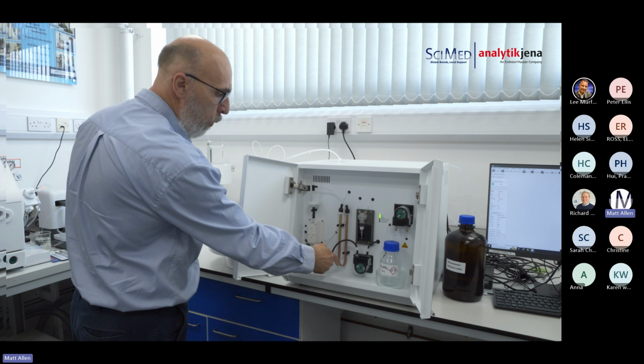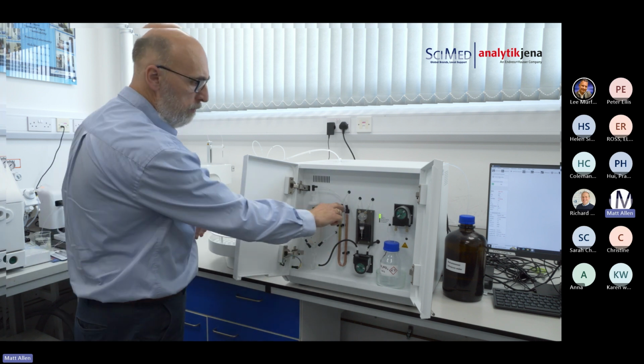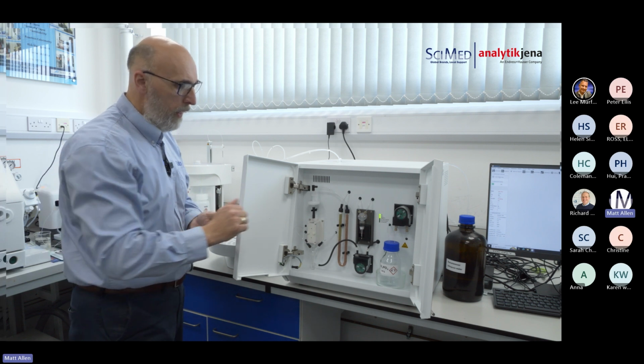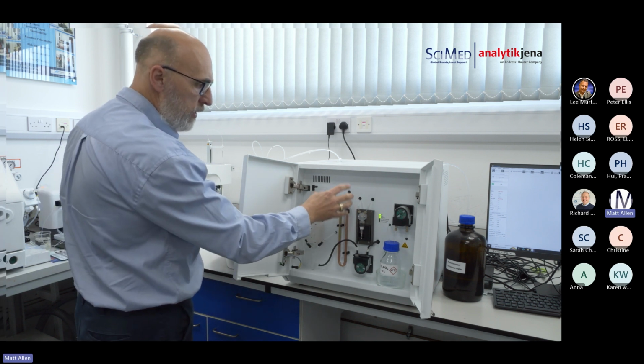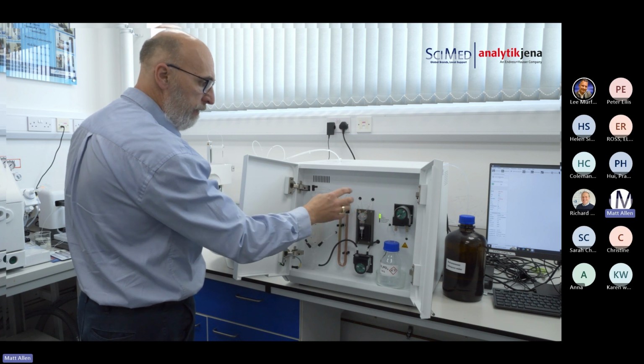So this is brass and copper wool. What we typically say is that once this goes black down one side, that's when you'd normally replace it. Again, push fittings, tube comes out, replace it. Very, very simple to do for the end user. But then on the 33 and the 43 in particular, this is the heart of the system. This syringe pump here. It's a very, very accurate syringe pump, and because we're using flow injection as opposed to direct injection, it needs to be.